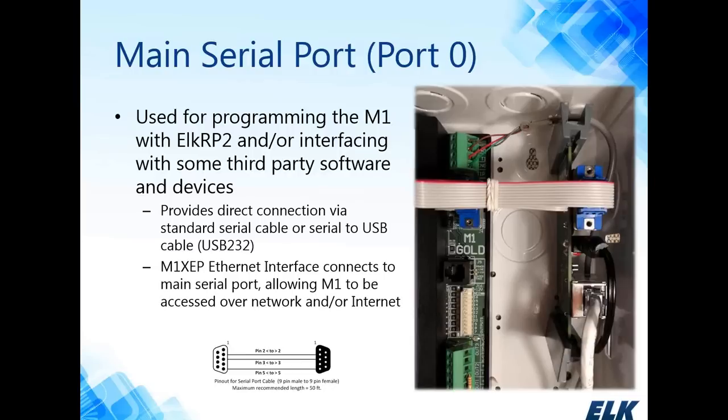You can connect the XEP module to the main board here on serial port 0, and that allows the M1 to be connected to the local area network or accessed through the internet. So when the M1 is connected to the local area network, multiple devices can connect to the system over the local area network, RP, those third-party software or touchscreens and so forth. But once RP connects, it takes hierarchy over the connection, so those other devices' communication would be suspended during that time period.